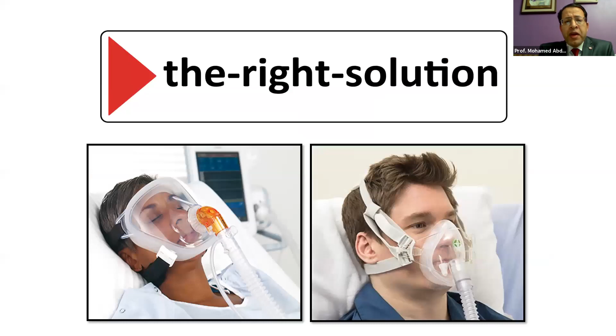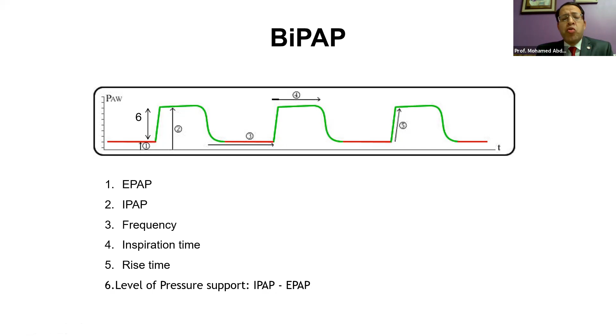What is the difference now between BiPAP and CPAP? BiPAP is continuous positive airway pressure with two different levels of pressure, while CPAP is continuous positive airway pressure at a single level. So we have two components in BiPAP, EPAP and IPAP. EPAP is responsible for oxygenation. So if you have a problem in oxygenation, you increase EPAP, and IPAP is responsible for ventilation. So if you have a problem regarding carbon dioxide, you increase the IPAP, and the difference between IPAP and EPAP is the pressure support, or the pressure needed to unload the respiratory muscles and augment the tidal volume.